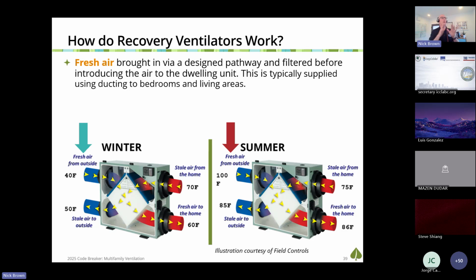And here's a quick graphical representation of the heat recovery part of a recovery ventilation. You've got fresh air coming in from outside, and then we're showing a winter scenario on the left and a summer scenario on the right. So in the winter scenario, cold air, let's say it's a 40-degree day. Our indoor air is 70 degrees. That's shown as the stale air from home airstream. So what the recovery ventilator is going to do is warm up that 40-degree air with the outgoing 70-degree air. And instead of 40-degree air coming into the house, you're getting 60-degree air in.